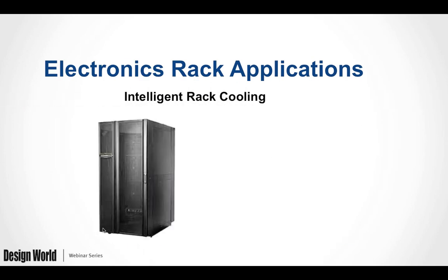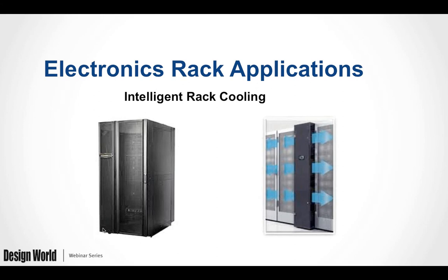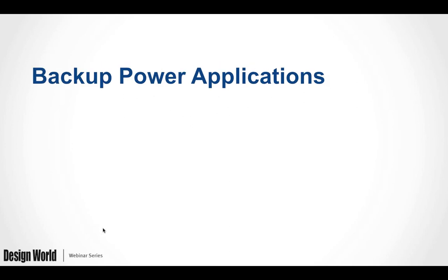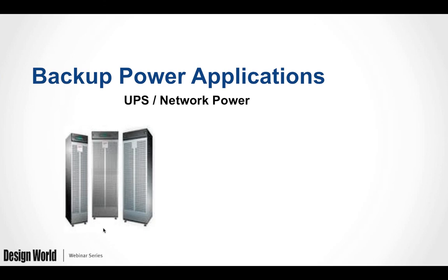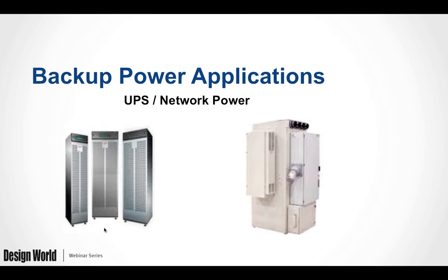Rack systems are designed to allow many different network devices from different vendors to be co-located in controlled environments. These rack cabinets move lots of air, and dirty air filters inhibit airflow, so it's important to inspect the right filter and be diligent with maintenance. UPS systems that provide backup power for buildings, data centers, and telco networks are more commonly operating in standby mode, so the fans only kick on when the grid goes down and backup power is needed. Some models exercise weekly, which creates dust generation. Backup systems operate from time to time when grid power fails, and filters do get dirty, so they need to be checked and included in maintenance procedures.